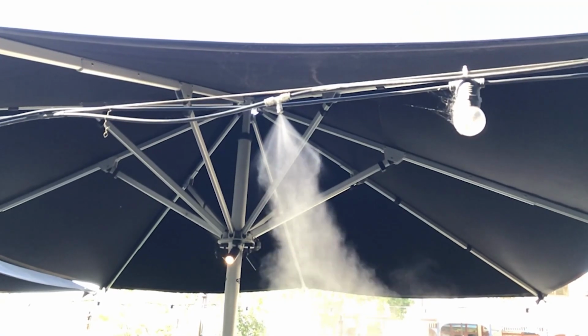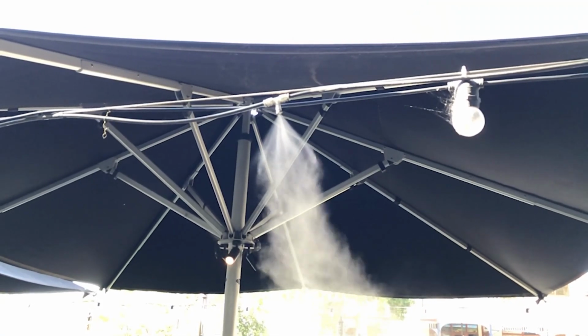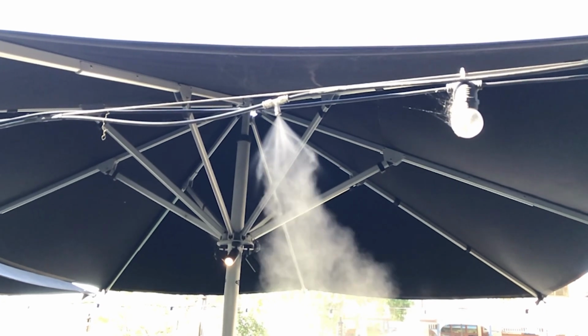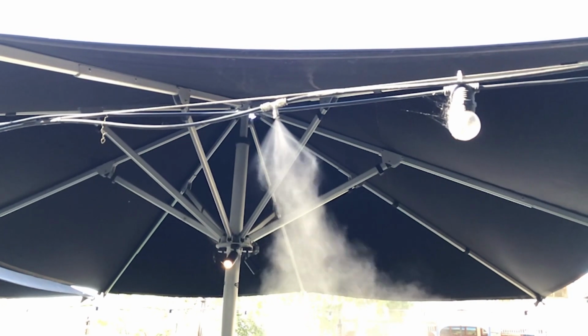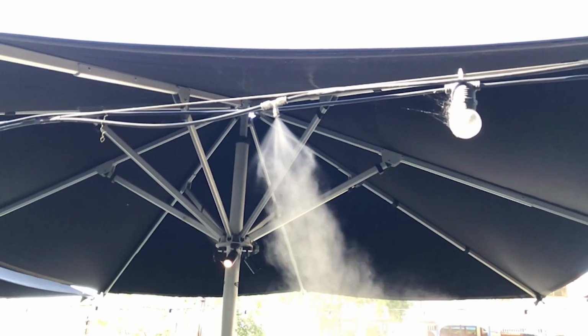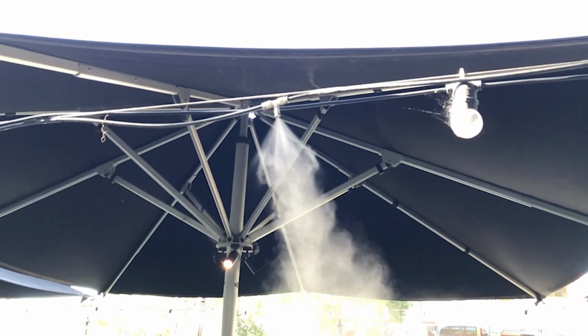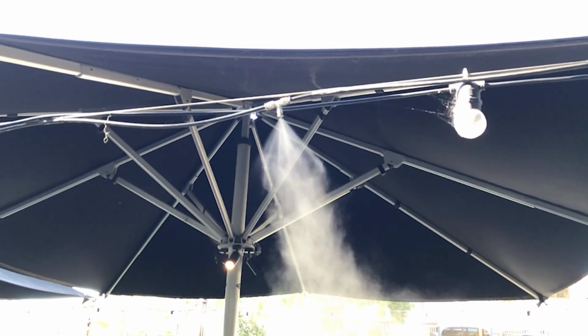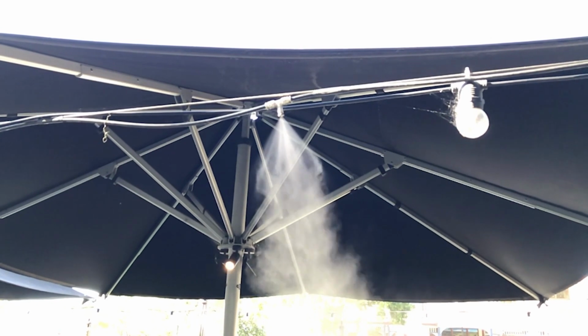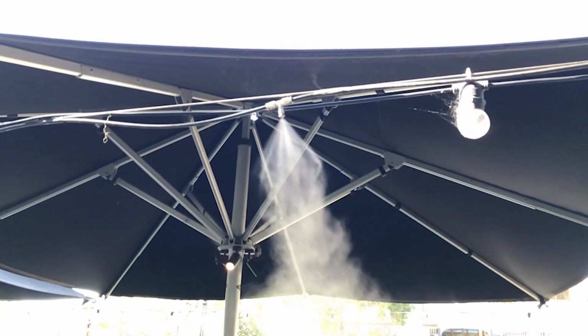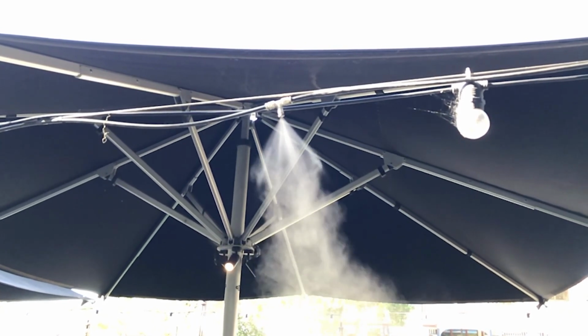Water has a very high heat of vaporization, which is the amount of energy required to change a given amount of water from a liquid to a gas. And so evaporative cooling is an efficient means of extracting heat from the air. A high pressure pump is required to produce such a fine mist, with droplets as small as 5 micrometers in diameter. There are two main advantages of using such fine drops.